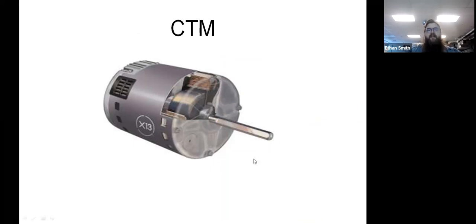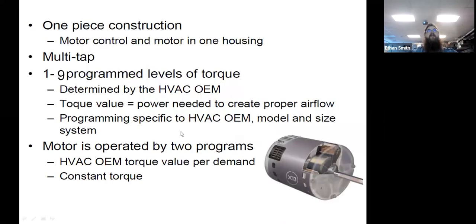Okay, let's talk about CTMs really quick. So a CTM is a DC driven motor. So it's got all the efficiency gains of a variable speed motor, but it has one-tenth of the brains. These have up to 9 programmed levels of torque. These do not adjust for CFM based on static pressure, but you get the efficiency of that motor. You don't have quite the CFM range, and they suffer with high static, but you get a lot more efficient motor. This is why we had the FER rule a couple years ago, where it took all of the PSC motors out of blowers in furnaces. And we went to these constant torque motors from those PSC motors.